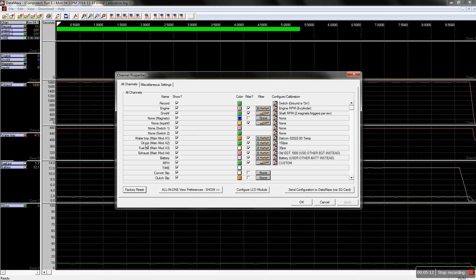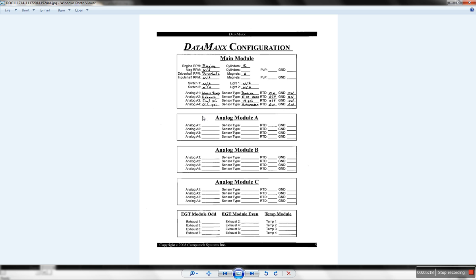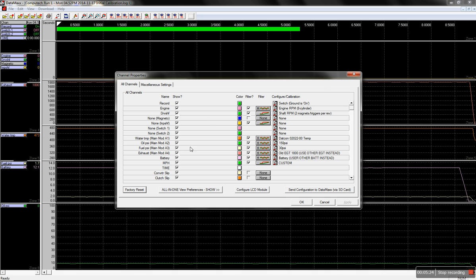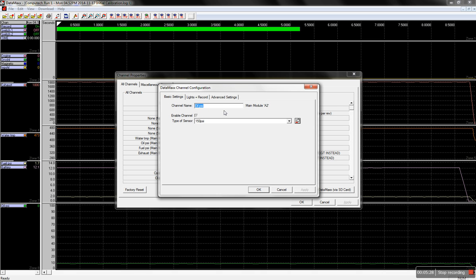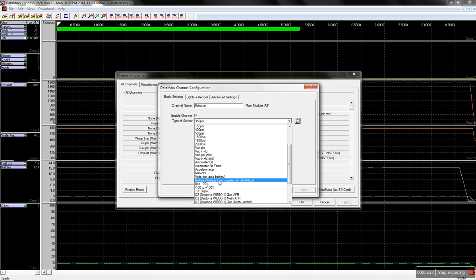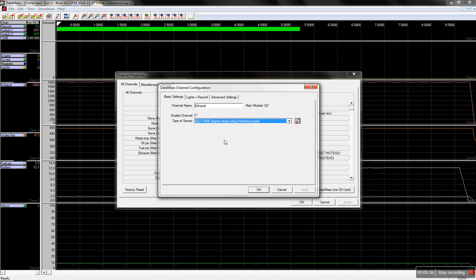The next line is main mod A2. The data logger right now thinks we have oil pressure plugged into it. But if we look at our configuration sheet, we see we actually have exhaust temperature plugged into it. So we need to change that. So we're going to come over here, click on the calibration button, and we're going to hit exhaust. From the type of sensor, we're going to select the EGT 1800 degree temperature range.